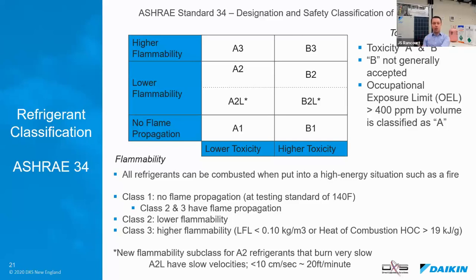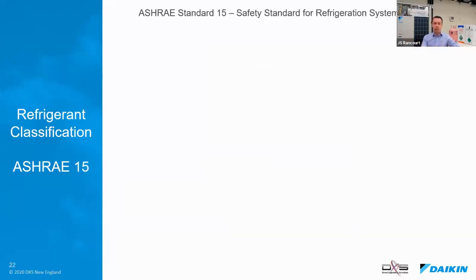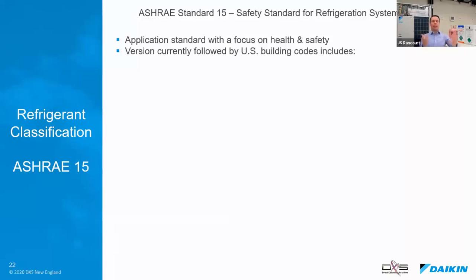Now, later we'll get into it, but the standards already talk about A2L, but the building codes have not yet adopted those standards. That's why, in terms of the building codes today, in whatever state you're in or in Canada, the 2L category isn't yet fully accepted. The second standard is ASHRAE 15. This is the equipment application standard for health and safety of refrigerants. And ASHRAE 15 does a couple things.